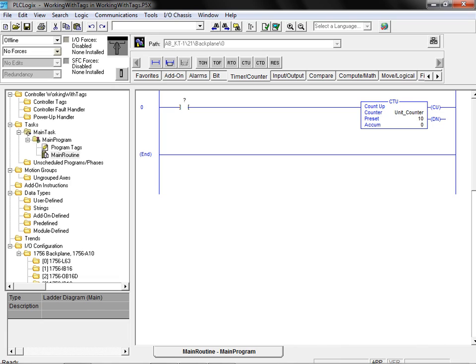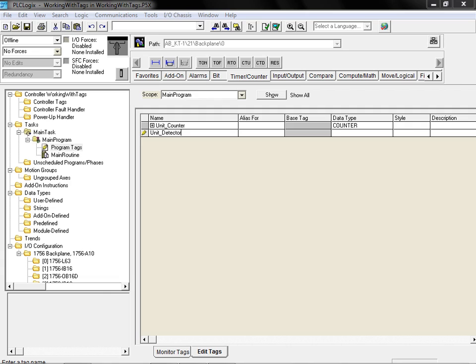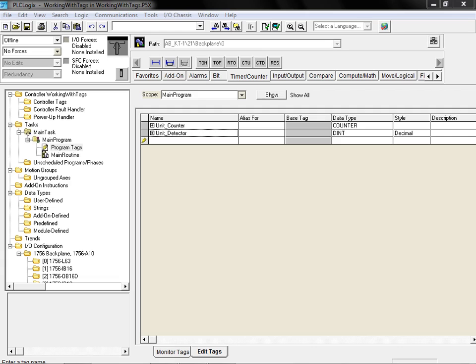We'll now return to the tag editor and create a second tag for use with the contact on this rung. As we've done previously, we enter the desired tag name in the name field provided. This time, our newly created tag is intended for use with the contact on our ladder rung that provides stimulus for the counter. We will therefore associate this tag with an actual physical IO address. This type of tag is referred to as an alias tag.